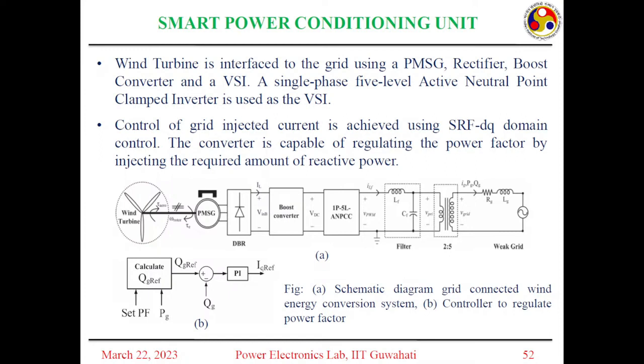Traditionally we only inject active power to the grid. Now we have an example where we are injecting reactive power. Of course, you can change the algorithm so that it also injects some harmonic current if required. In this case we have a small change in the control algorithm. We have a power factor setting, and according to the power factor setting we can calculate the reactive power to be injected into the grid, and accordingly we can calculate the IQ reference.